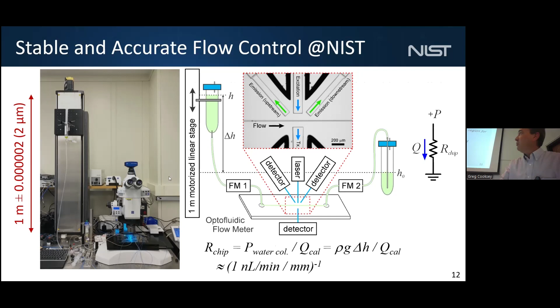And we are controlling the conductance of the system by the fluidic resistance of the chip. So we define a chip that has a pretty high fluidic resistance, about half a meter length of a 20 micron wide channel, to ultimately get to a conductance magic number here. We get about 1 nanoliter per minute change in flow for every millimeter we change the height of that stage. And we calibrate this at the fastest flow rate using a conventional, well-calibrated commercial system. So that's where we get 5% uncertainty at 1 microliter per minute.